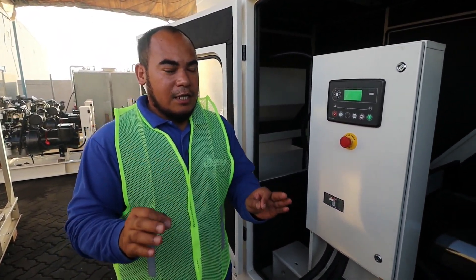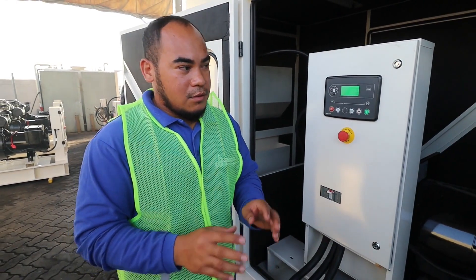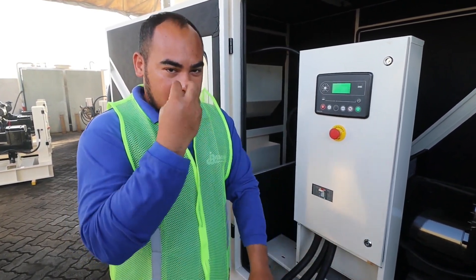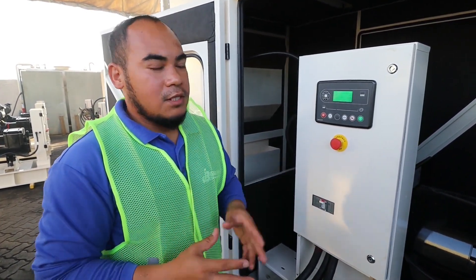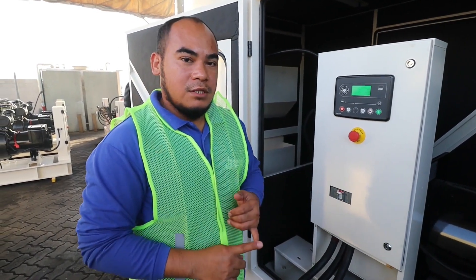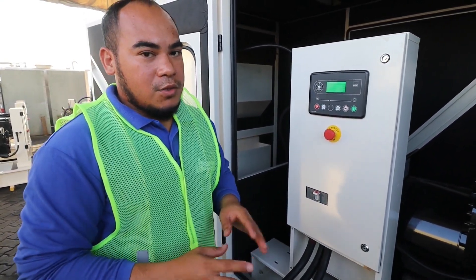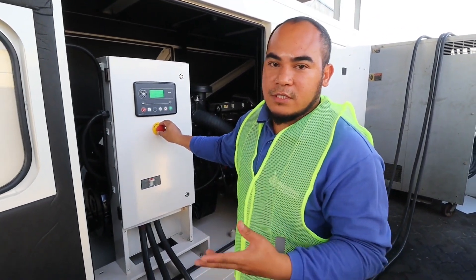As you can see, there is a lot of black emissions and also the engine is hunting. You can see the engine is like bumping — there is movement showing that there is hunting. Once I put the load, you can also see the movement of the engine, which is not good for your generator because it will affect your voltage and it will affect your frequency. So we need to fix the RPM. We're going to the other side in order to adjust this stability.